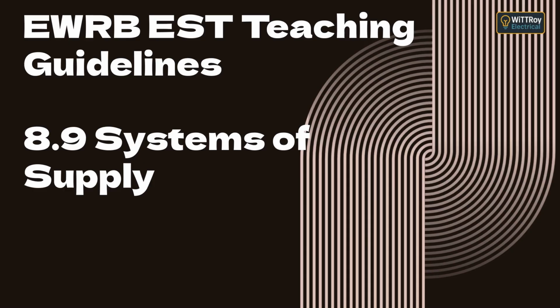2. Two-phase consumers, less common today, but sometimes used for medium-sized loads. They use any two of the three phases, giving a line-to-line voltage of 400 volts. 3. Single-phase consumers. Most homes and small businesses use single-phase supply, taking one phase and the neutral, giving 230 volts. Each of these supplies comes from the same three-phase transformer, which is star-connected on the secondary side with the neutral earthed through the main system. Topic D, advantages of balancing the load over three phases.